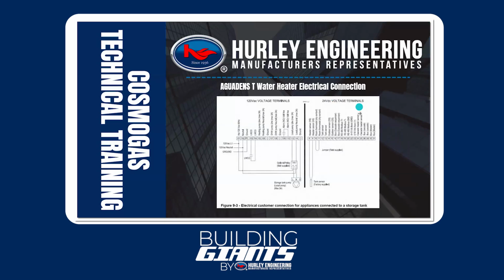We brought it up earlier. I just want to show here, if you go over that 3 amp when you're putting in your pumps, this would be how you would attach an isolation relay so that you're not running more than 3 amps through the local relays and fuses. You'll notice these are the terminals on top of the boiler, and the left hand side is our high voltage or 120-volt terminals, and the right side is our low voltage or 24-volt terminals. That would be where our sensors are tied in. The jumper is field supply. This would be possibly stops or anything you would need to disable and shut it down. You could remove the jumper and tie into those terminals instead.